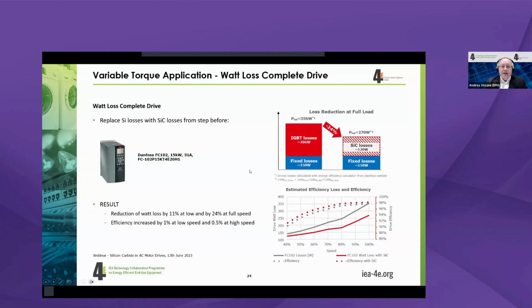Now, if this would be applied now to a typical 15 kilowatt drive, this would mean that the total losses will be reduced from 356 watts at the nominal point down to 270 watts. And at some lower speeds, we will also have between 11 and 24%. We also have 11% of reduction in losses.